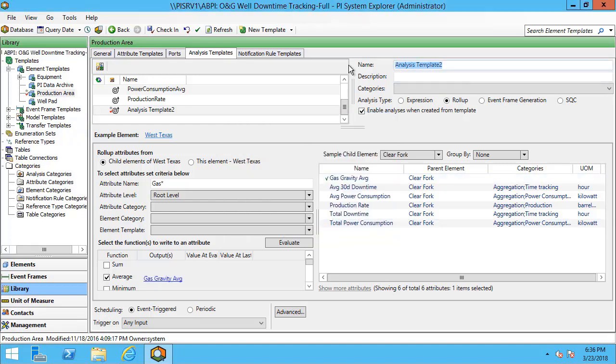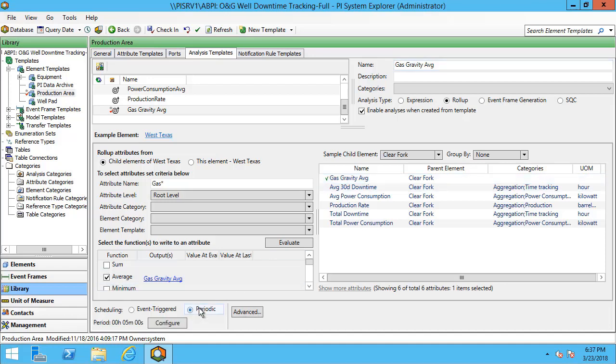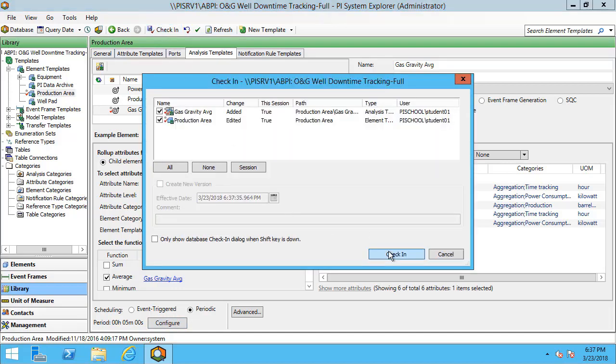I can also change the name. I'm going to change my triggering criteria to be periodic. And that's because this is for my entire production area. Since all of my well pads and all of their child attributes are event triggered, that means any time any of these gas gravity events comes in, it would then trigger my production area if it were left as event triggered. By changing it to periodic, it means that my calculation will run less frequently, but I'll still get updates every five minutes if I leave it as the default setting. I'll check this in.